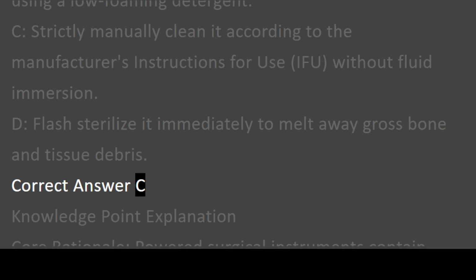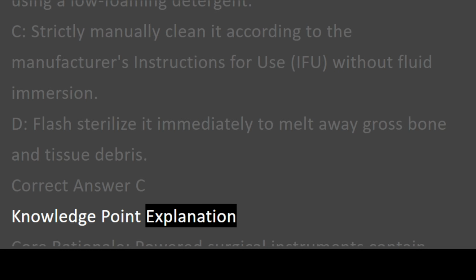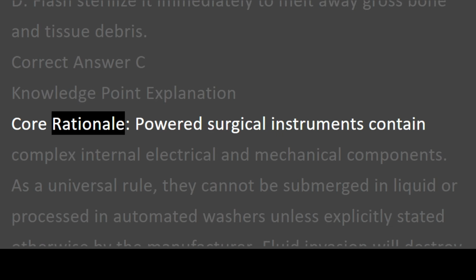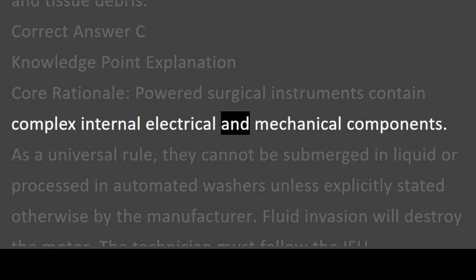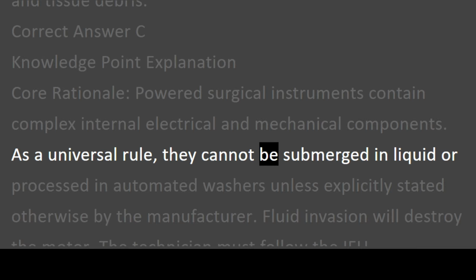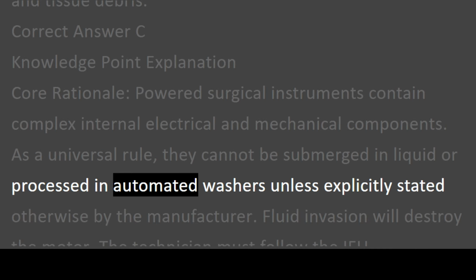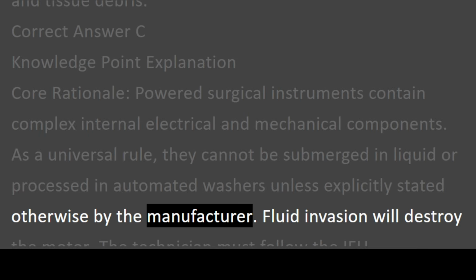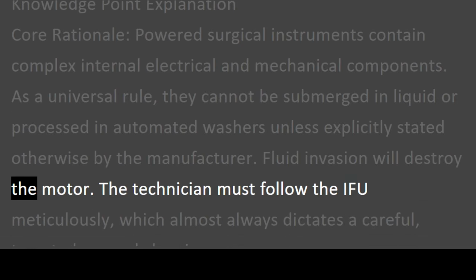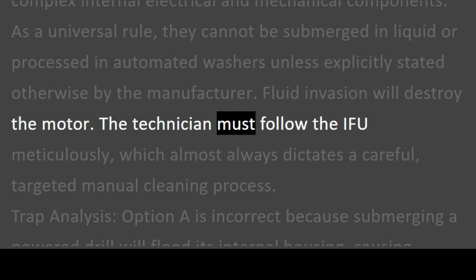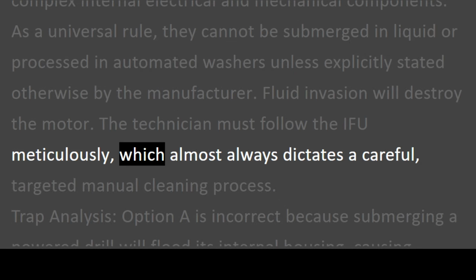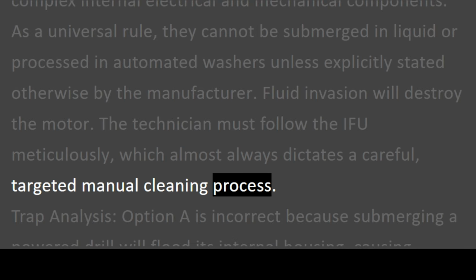Correct answer C. Knowledge point explanation. Core rationale. Powered surgical instruments contain complex internal electrical and mechanical components. As a universal rule, they cannot be submerged in liquid or processed in automated washers unless explicitly stated otherwise by the manufacturer. Fluid invasion will destroy the motor. The technician must follow the IFU meticulously, which almost always dictates a careful, targeted manual cleaning process.